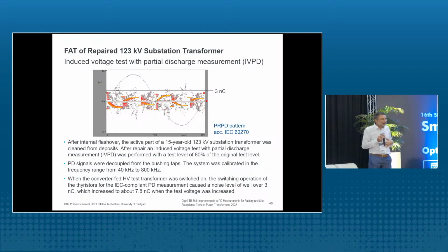Yeah, at the end, they put everything together after cleaning in this way, and then they did the factory acceptance test. The factory acceptance test was more or less checking, is the testing voltage okay? So is there no breakdown during the test? But I said, we have also to do a partial discharge test on this transformer. And then they said, we cannot do a partial discharge test because our testing transformer is excited by a power converter. And the power converter, of course, has thyristors for switching of the converter. And these thyristor switching gives PD pulses, or let's say gives electric pulses, which are detected by the PD measuring system.